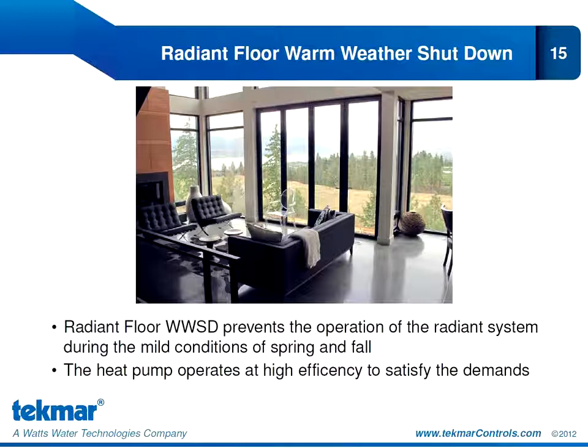And after all, this is when our heat pump is operating with a pretty high efficiency advantage. So let's use that while we can, while we're getting that efficiency bonus out of it, and hold off the radiant system until we actually need it when the outdoor temperature is colder.